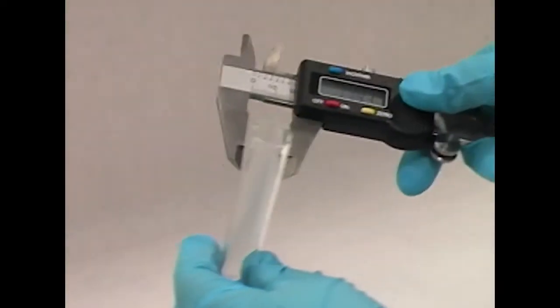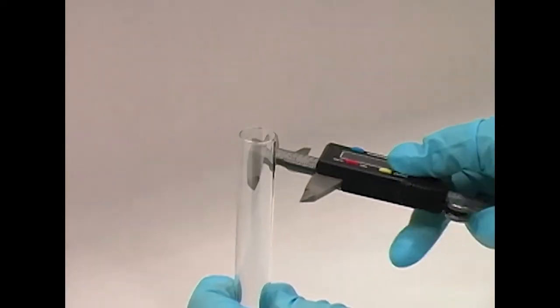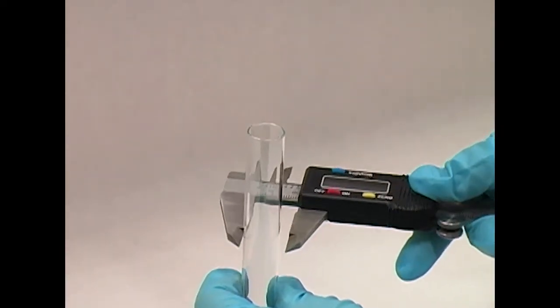Repeat this process with several sample test tubes because the height and outside diameter can vary by a few tenths of a millimeter between sample test tubes.